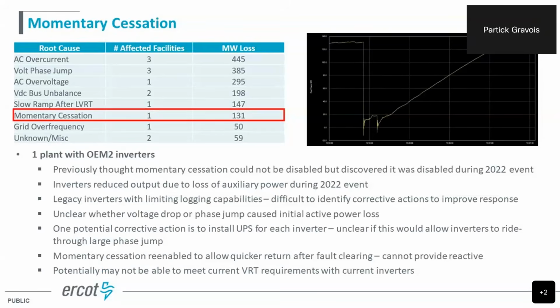So again, this is a legacy inverter, an older plant. What they found out was that it was actually a loss of auxiliary power that occurs when there's a large phase jump. They actually did have momentary cessation disabled during this event, but the loss of auxiliary power caused these inverters to trip. It's very difficult to determine from their logging capabilities if it was due to voltage magnitude below 0.9 or if it was a phase jump.